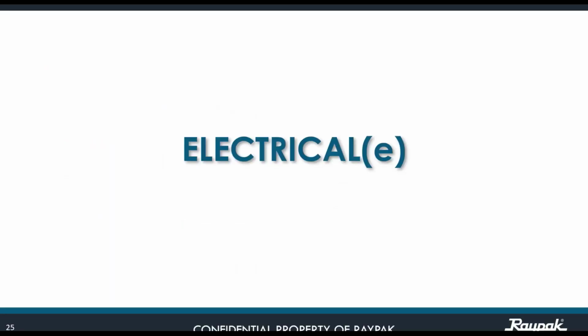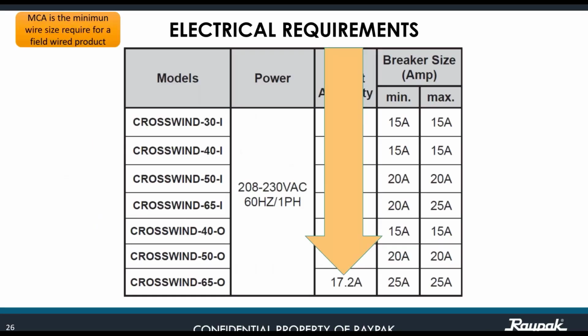Okay. On the electrical side, there are minimum requirements called the minimum circuit ampacity. If you notice, the first four models that I am showing here are for the inverter type. The rest are for the on and off, which is not really part of this class because we are just moving the inverter type in the US.